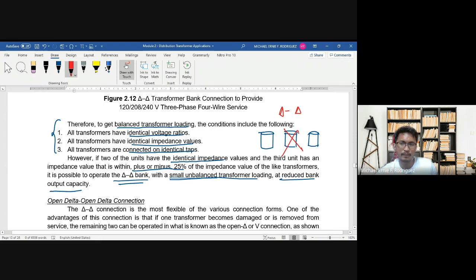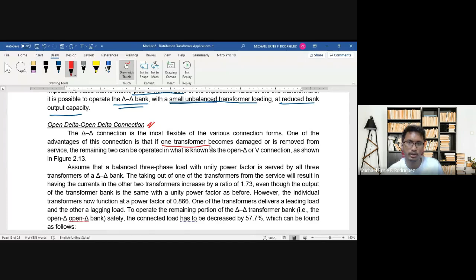So if one transformer is damaged or removed, the transformer bank can still operate, but the connected load must be decreased by 57.7%. For example, if you had 100 kVA supply before, for the delta-to-delta bank to keep operating, the load must be reduced to only 57.7 kVA.